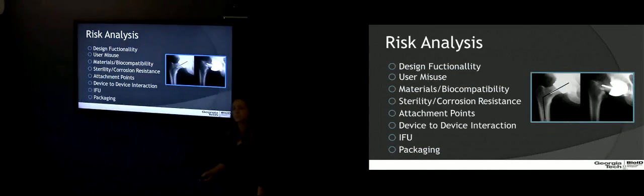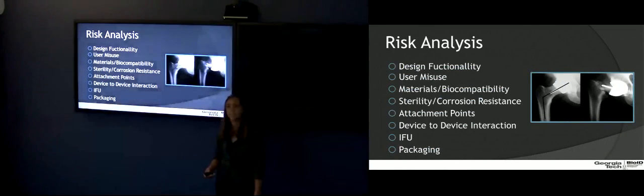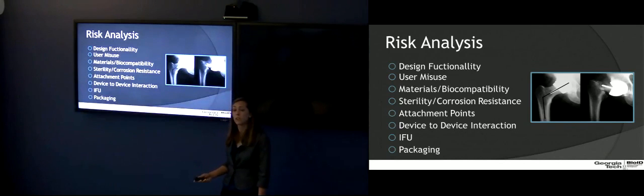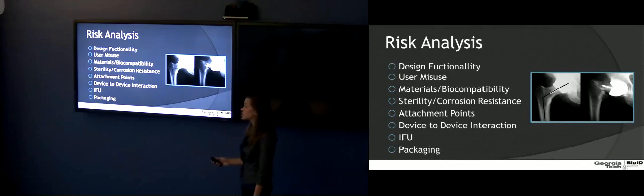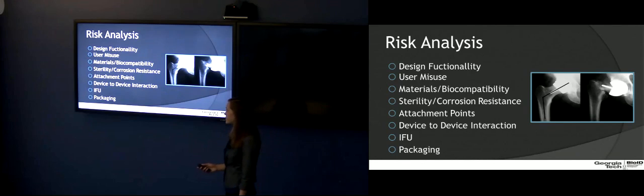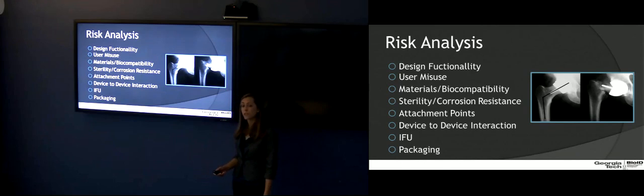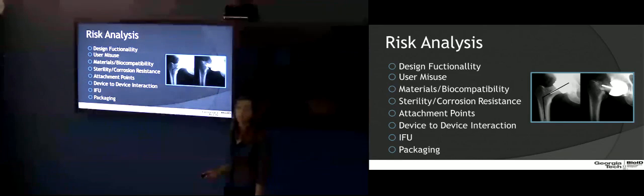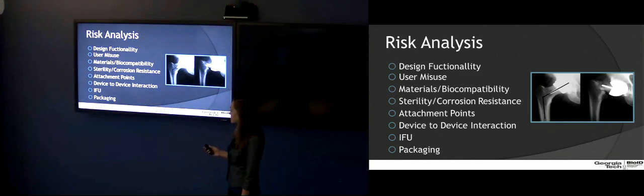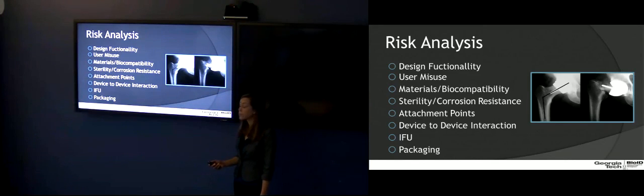So risk analysis. The purpose of risk analysis is to identify certain functions that might go wrong in your product and to mitigate these risks. So what we looked at was the design itself, the overall design and how it functions. If the user misuses the device, what could happen? Also the materials the device is made of, it's made of stainless steel, and that short-term biocompatibility with the incision. Its sterility and the corrosion resistance in its environment. Also the jig's attachment points on the femur, we did not want it to compromise that femoral neck bone integrity. Also the device-to-device interaction, so how it interfaces with that guide wire. And lastly, its instructions for use and packaging.